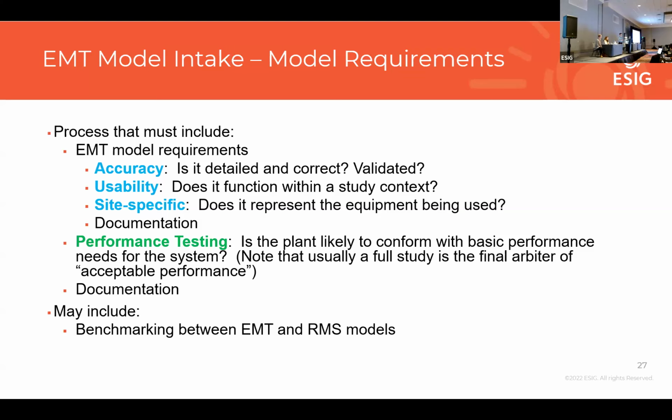The third big point there is whether it's site specific. And what we mean by site specific really does change as the project matures. So at the initial model submission stage, usually there is nothing built yet. Depending on when you're collecting models, there may or may not be something built. So that site-specific check will mostly be referring to whether it correlates with the rest of the data that's been submitted. Does the information match what's in their application, for example? Does it match what they submitted for their phasor domain model, et cetera?